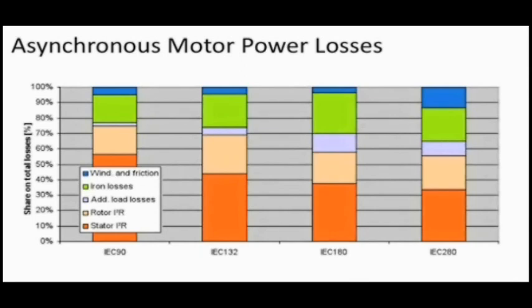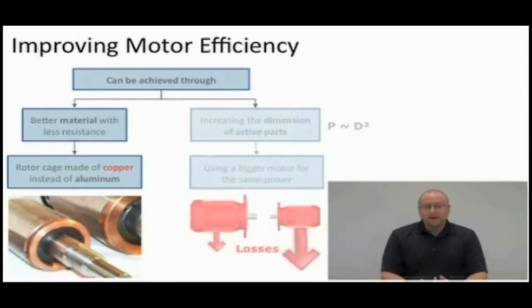That's the current flowing through the motor, creating heat, which is lost energy. There's a couple of other things that you can see there, like in the dark blue at the very top, those are the friction losses in the bearings. We could put high efficiency, low friction bearings in the motor, but in the big picture, that's not really going to make that much of a difference. If we look at the other losses, like the copper losses, if we attack those areas, we can make a big difference. So how can we attack those losses, and how can we change the efficiency of an asynchronous motor?